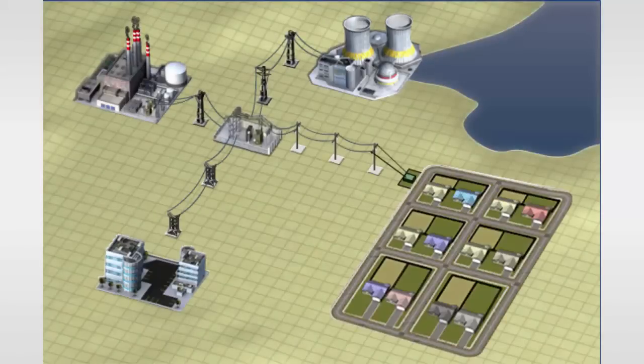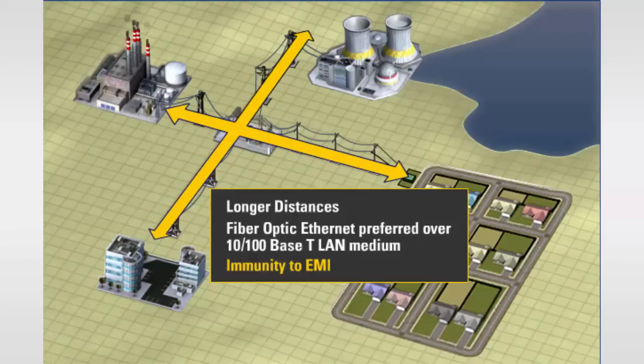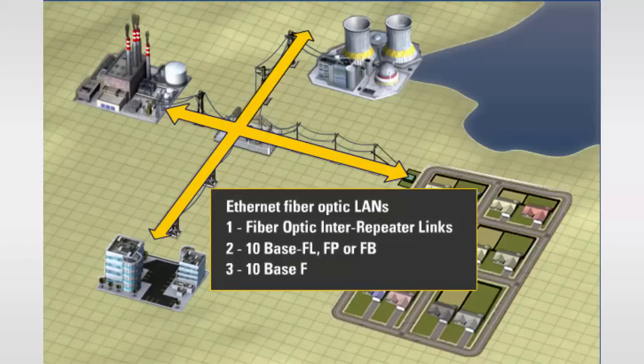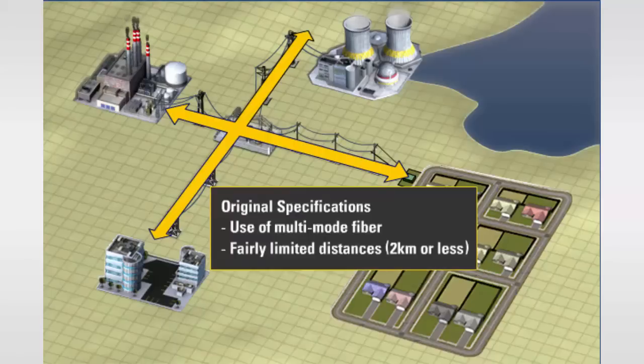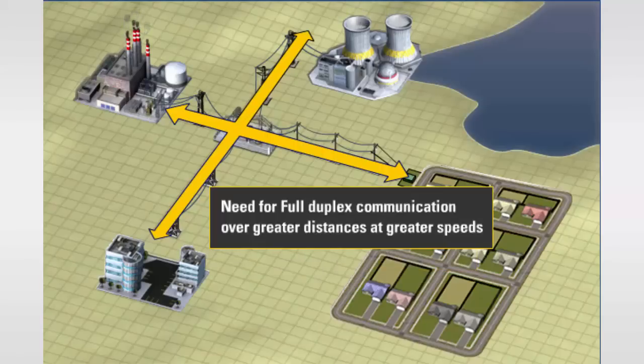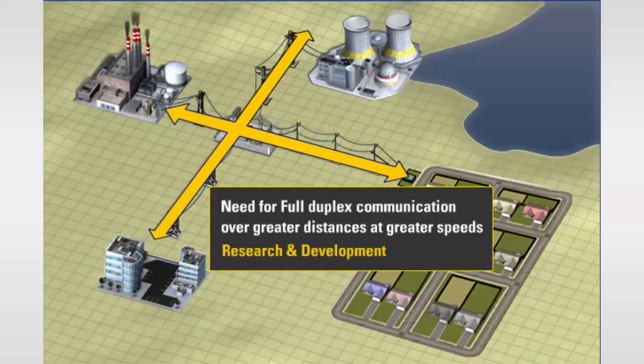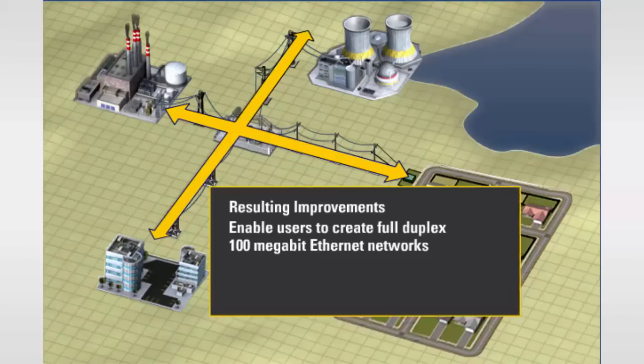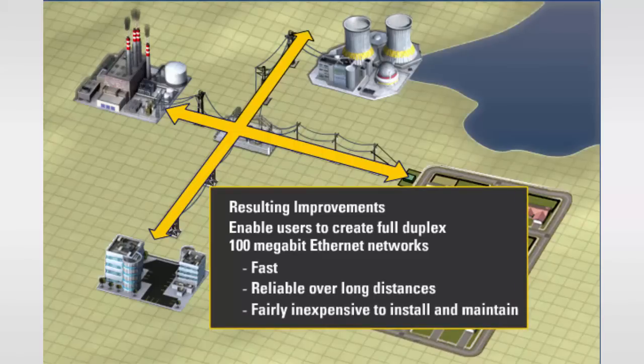In power system applications where longer distances are involved, fiber optic Ethernet is preferred over the more popular 10/100BASE-T LAN medium due to its immunity to EMI. The higher cost and difficulty of terminating fiber cables allows twisted pair to continue to be used where appropriate. Ethernet fiber optic LANs were first referred to as fiber optic inter-repeater links, later changed to 10BASE-FL, FP or FB, and then finally 10BASE-F. The original specifications were based on the technology of the mid-80s, calling for the use of multimode fiber with fairly limited distances of 2 km or less. The need for full duplex communication over greater distances at greater speeds sparked research and development, resulting in full duplex 100Mbit Ethernet networks that are fast, reliable over long distances, and fairly inexpensive to install and maintain.